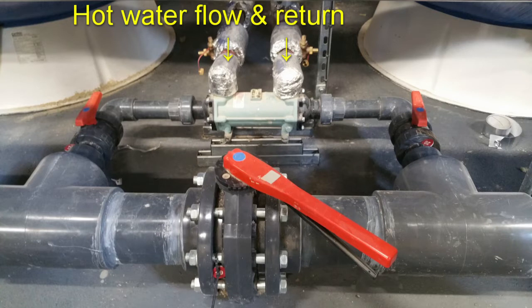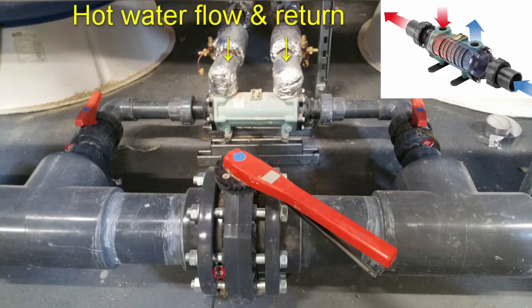Those lagged pipes, or they should be lagged, are the flow and return pipes from the heating system. So from your hot water heating system, there'll be very hot water feeding into that heat exchanger and then being flowed through it and then coming out and going back to the heating system on a return. And then there'll also be pool water flowed through the heat exchanger, picking up the heat from the hot water heating system, and then carry on.